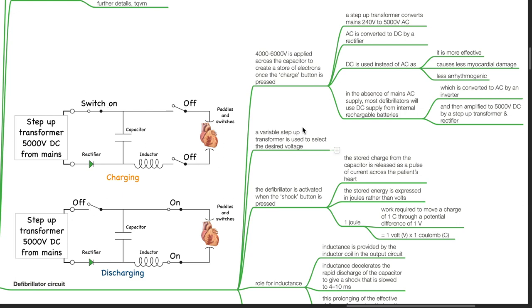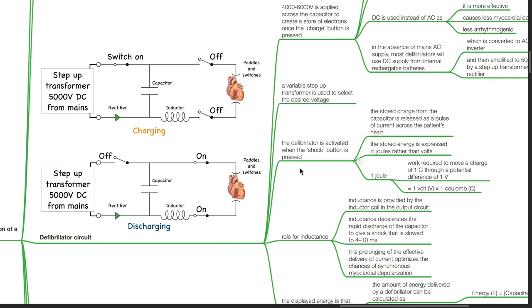In the absence of mains AC supply, most defibrillators will use DC supply from internal rechargeable batteries, which is converted to AC by an inverter, then amplified to 5000 volts DC by a step-up transformer and rectifier. A variable step-up transformer is used to select the desired voltage. The defibrillator is activated when the shock button is pressed, and the stored charge from the capacitor is released as a pulse of current across the patient's heart.